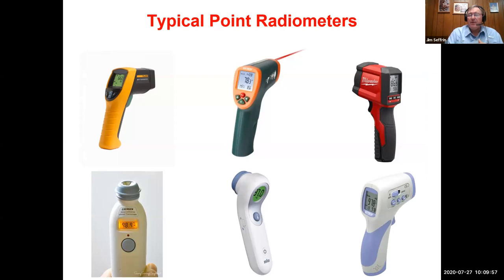Here we see an example of several typical point radiometers or infrared thermometers. The three at the top are industrial grade. They are meant for use for building or machinery inspections, while the three at the bottom are medical grade instruments. The one at the left is a contact infrared. Keep in mind, not all infrared instruments are designed to be non-contact. However, the two at the center and right on the bottom, they are medical grade. They are non-contact. So the three at the top are industrial grade. They are not accurate enough in order to produce acceptable results or to be used for human body temperature measurement, while the three at the bottom are. We'll talk more about that as we get into our slides a little deeper.